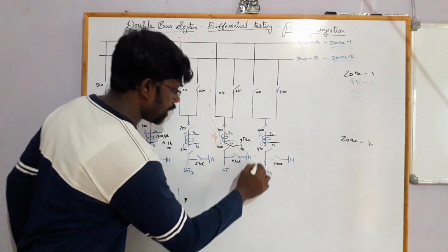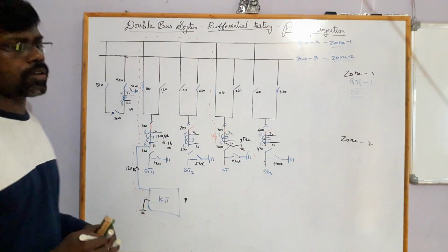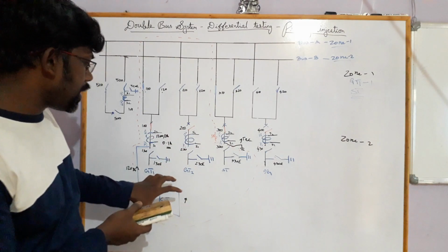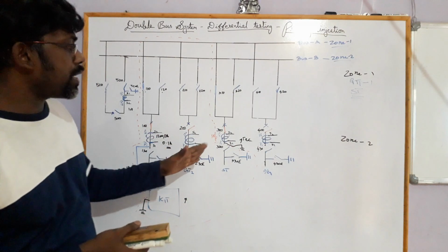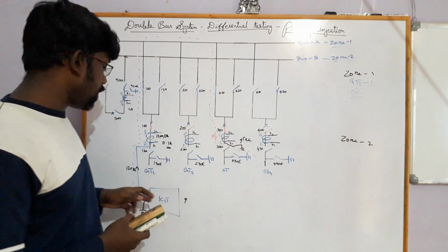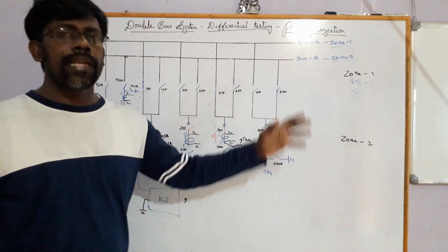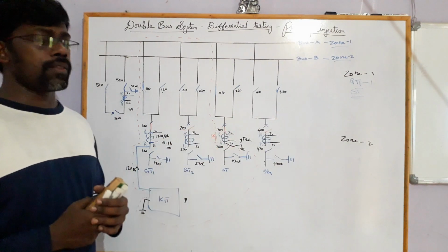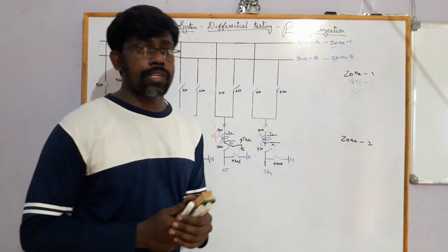From here to here, it will get a closed path automatically through earthing. By this method, we can keep the kit in one place and test all feeders by closing the switches one by one. Also, we don't need a very long welding cable, and the cable size can also be reduced by this method. Okay, fine. We go to testing now.